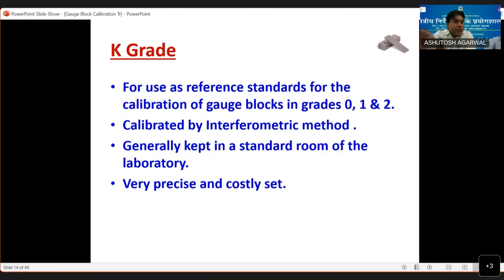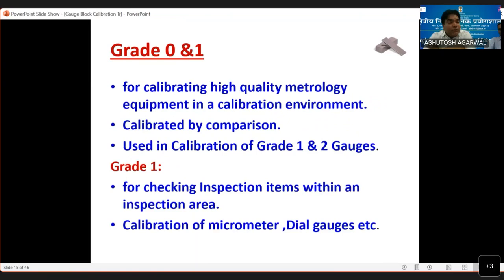When you do your second one, grade one or zero grade, not two. Grade two you cannot use for this. It is generally kept in the standard room, a very precise and costly set. The cost of this one and the K grade differ very highly. Then 0 and 1 are used only for calibration of high quality metrology equipment, only in a calibration environment. If you measure outside, it will not work. K is calibrated by interferometric method, but 0 and 1 are calibrated by comparison and used in calibration of 1 or 2. If 0, then 1; if 1, then 2.